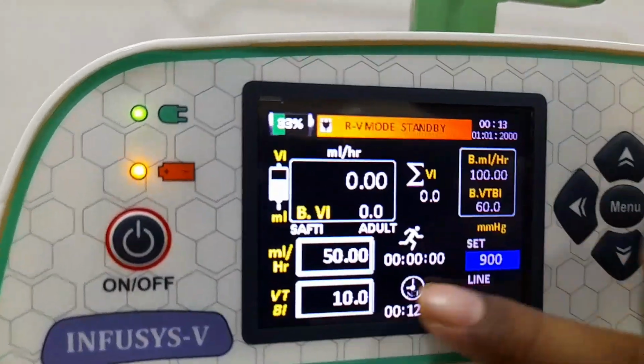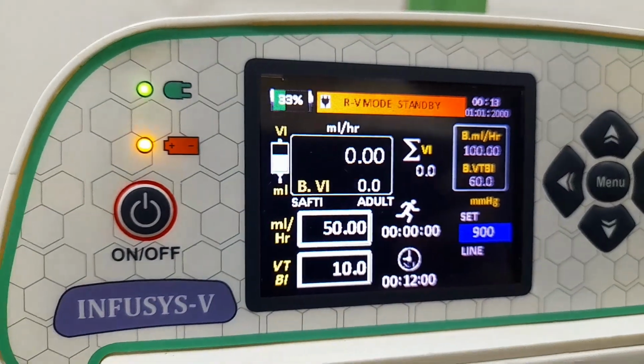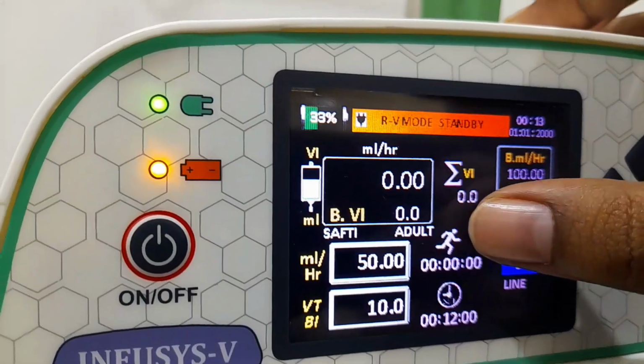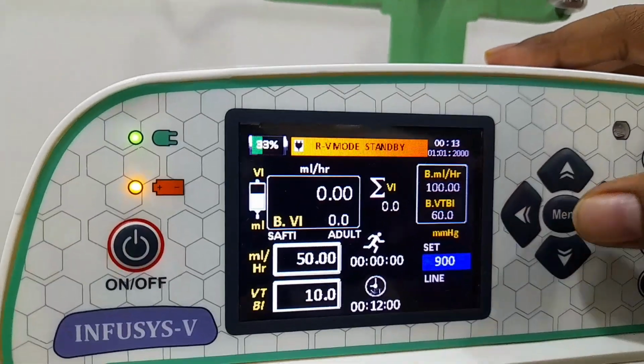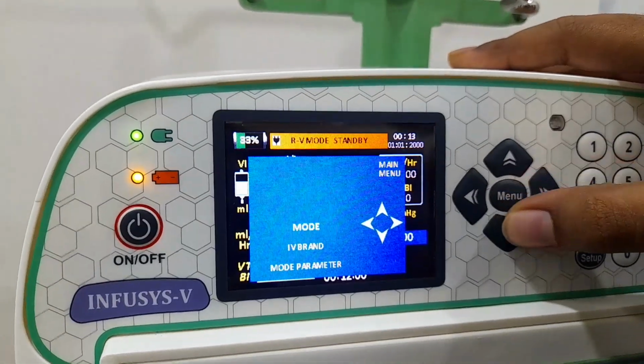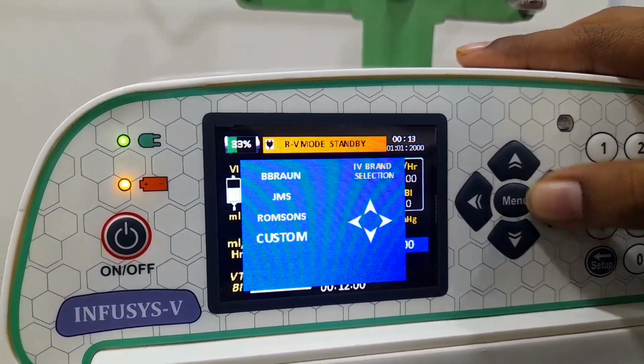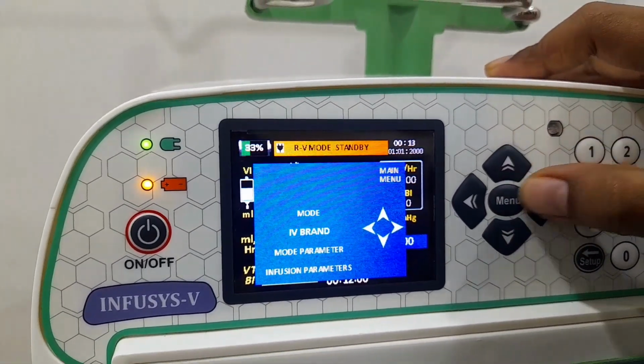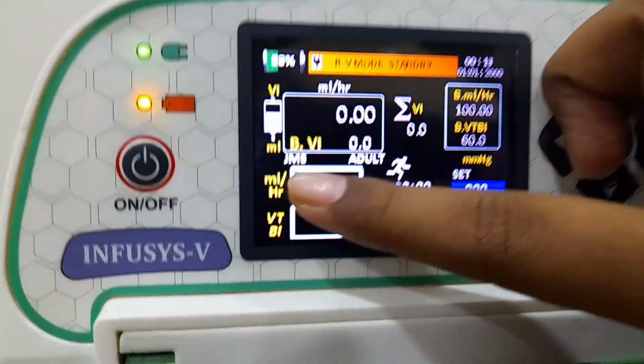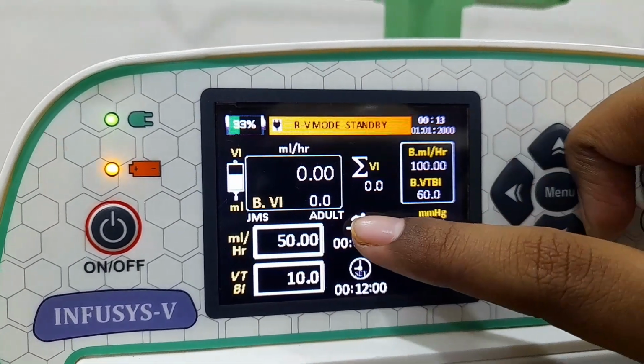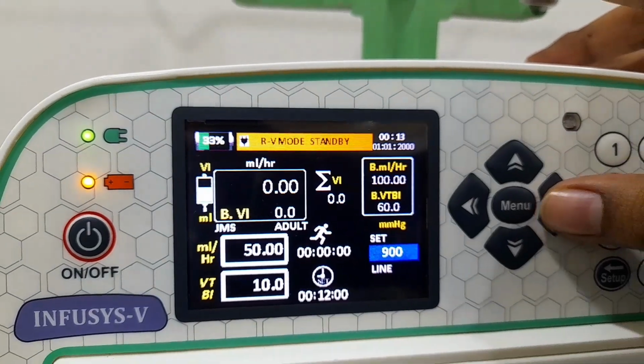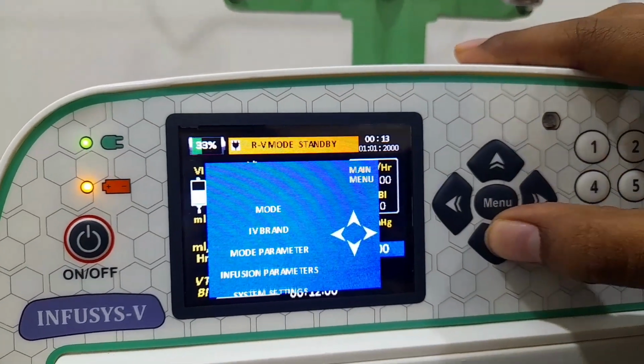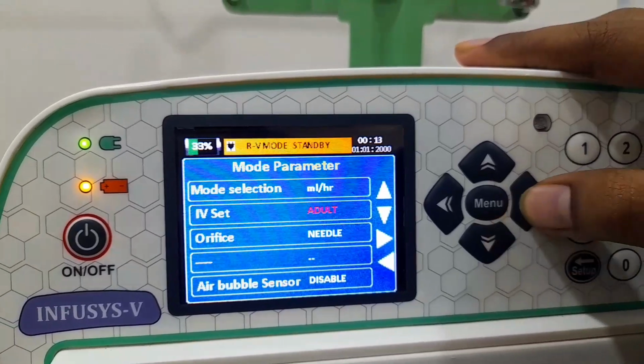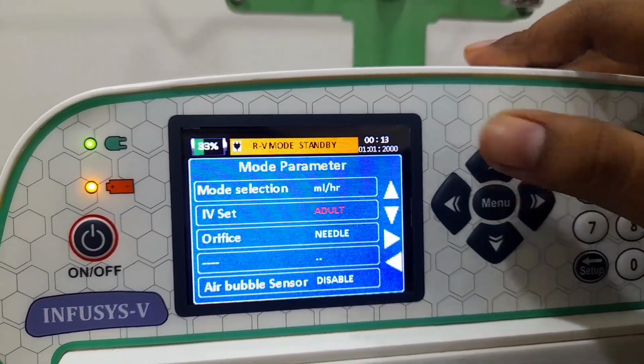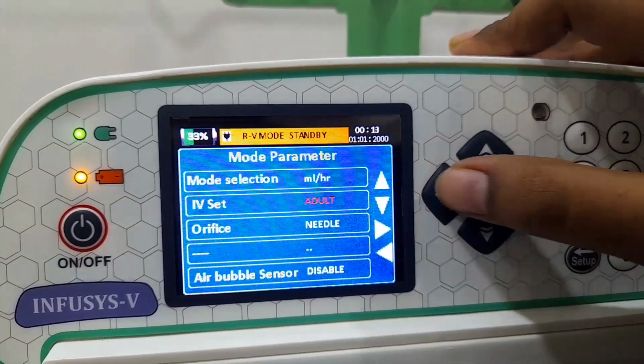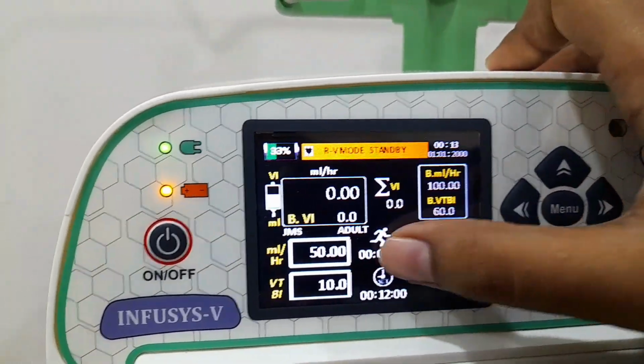After placing the IV sets, we need to select the IV set brand and IV set as adult or micro in the home screen. So press the menu key to enter menu options. Here we select IV brand using the right navigation key and select JMS using the up and down navigation keys. Select JMS because we use a JMS IV set here. Now we change adult or micro using the mode parameter. Enter the mode parameter and change adult or micro using the right navigation key. Once we select it, get back to the home screen using the left menu key and left navigation key.